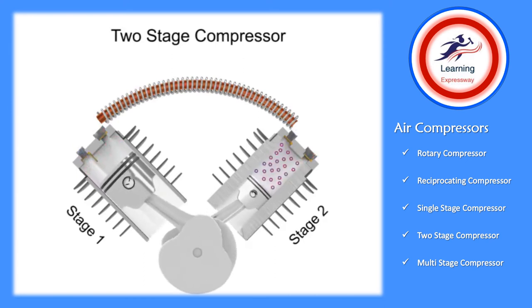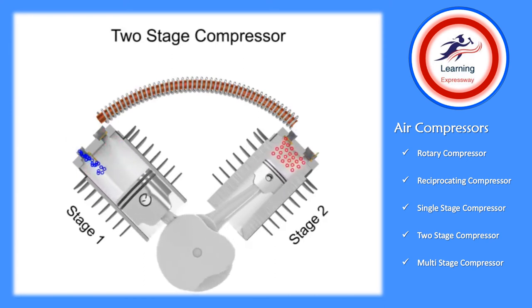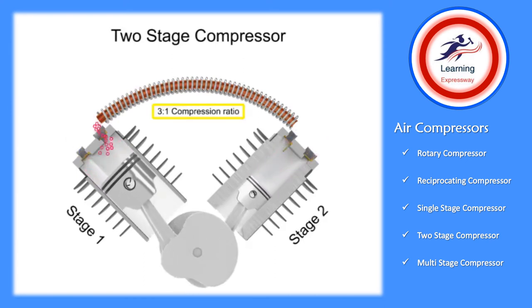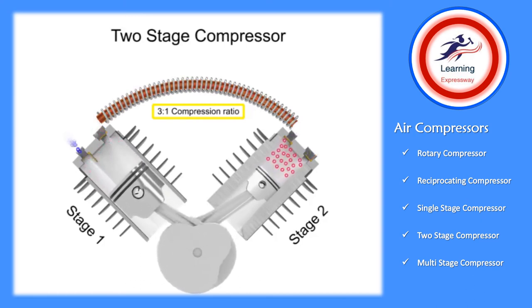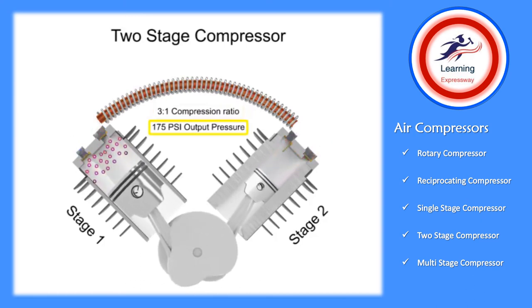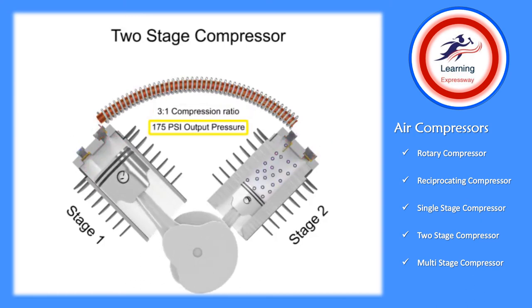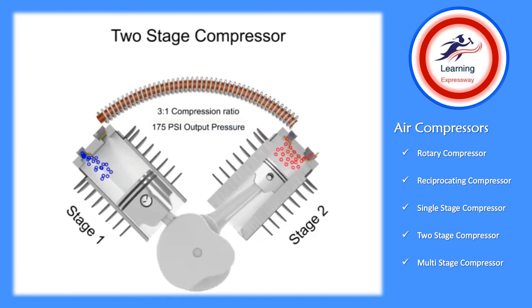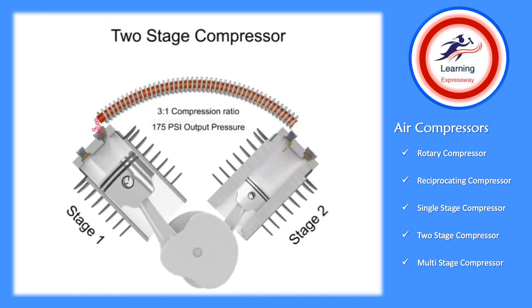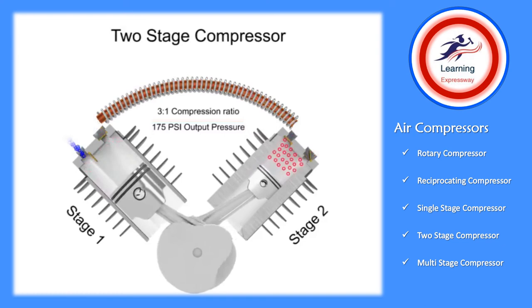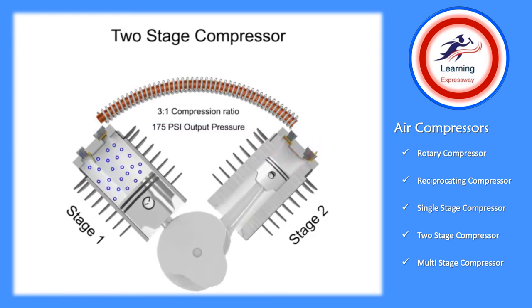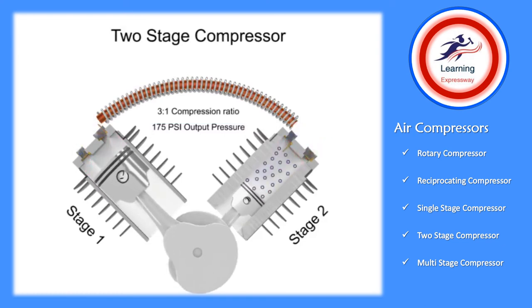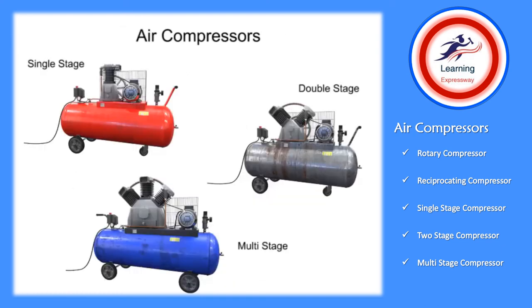Two-stage compressors have a compression range of 3 to 1 or even less per stage, but can operate up to 175 psi. They can also deliver more air at a higher pressure than single-stage compressors of the same horsepower. If pressures of more than about 175 psi are needed, multi-stage compressors should be used.